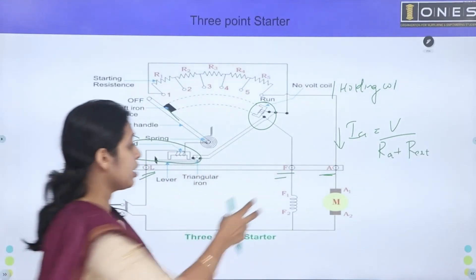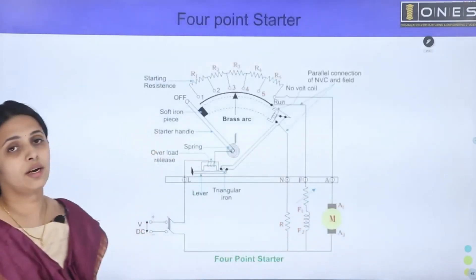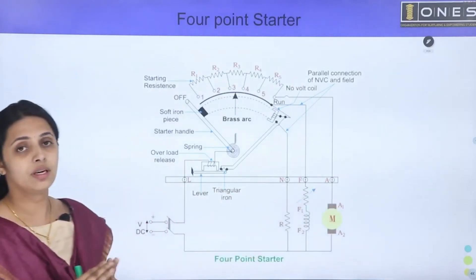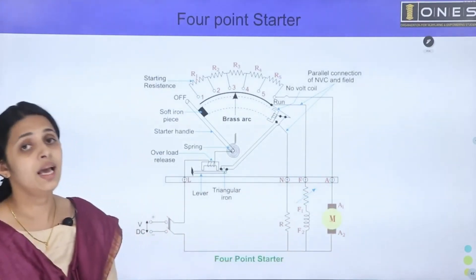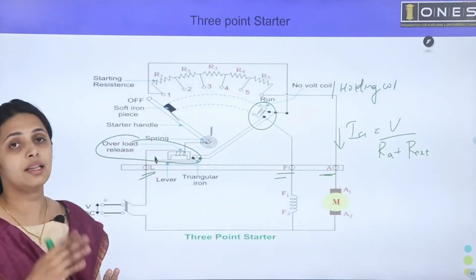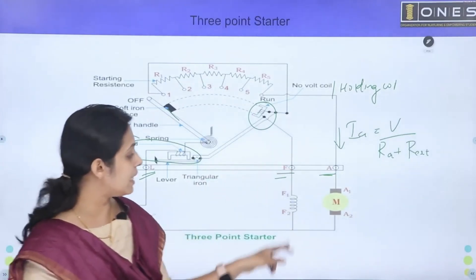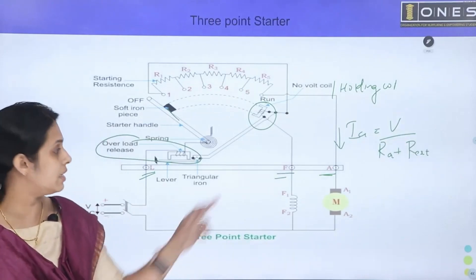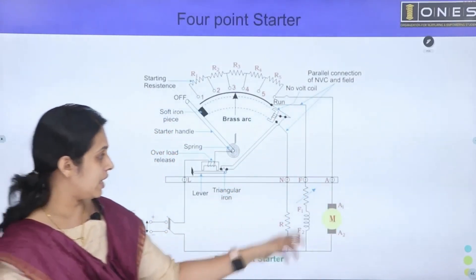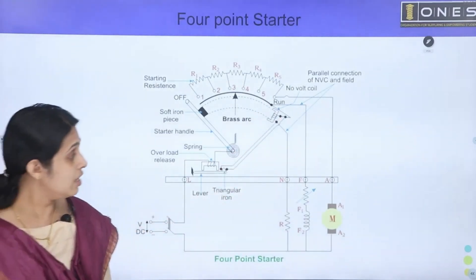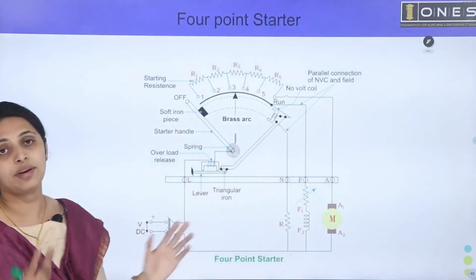In a 4-point starter, there are four terminals: L (line), N (no-volt coil), F (field), and A (armature). The advantage over the 3-point starter is that speed control above base speed is possible by weakening the field current. The holding coil is on a separate independent circuit, so reducing field current does not affect the holding coil.